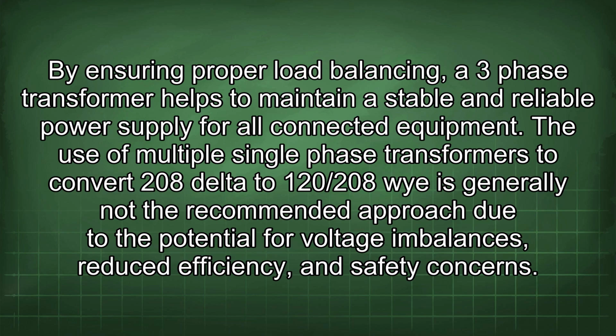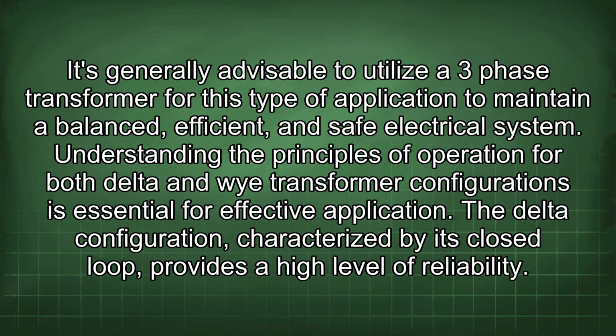The use of multiple single-phase transformers to convert 208 delta to 120/208Y is generally not the recommended approach due to the potential for voltage imbalances, reduced efficiency, and safety concerns. It's generally advisable to utilize a three-phase transformer for this type of application to maintain a balanced, efficient, and safe electrical system. Understanding the principles of operation for both delta and Y transformer configurations is essential for effective application.